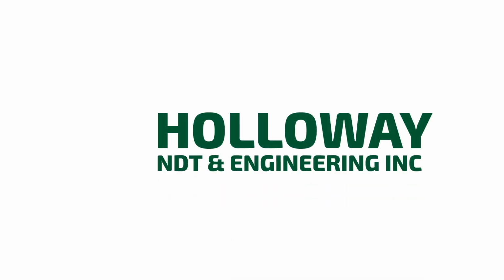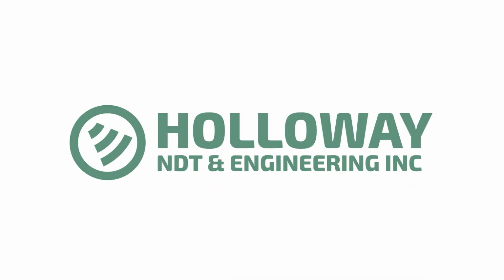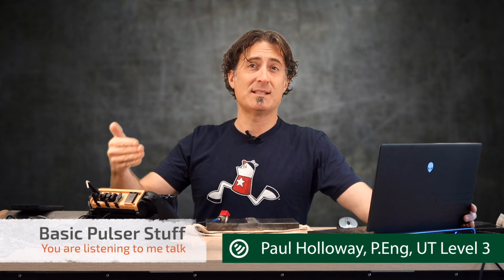Today we'll talk about the difference between a spike and a square pulser and exactly what is the pulse width. On your ultrasonic instrument, you've got a pulser which sends a signal to the transducer. It's probably a unipolar pulser, which means that it's going to send just a negative voltage signal, and you usually have the opportunity to choose between spike or square.